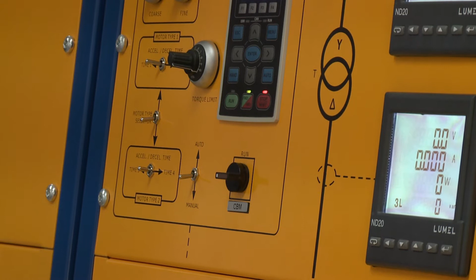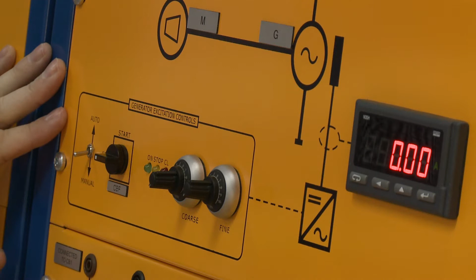Same with the generator, we have feedback, auto and manual, if we want to hold the voltage at the same level, or sometimes we want to see the voltage sync. In this case, when we want to synchronize with the grid, we keep these in manual because we don't want our equipment to fight against the grid. It won't damage the equipment, but we might get some trip.